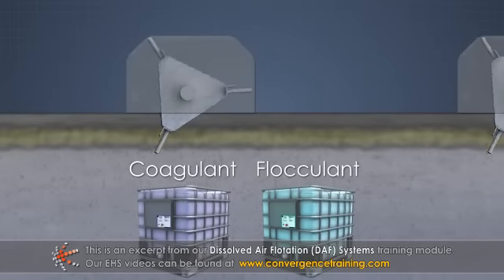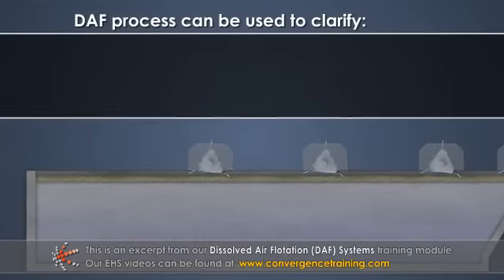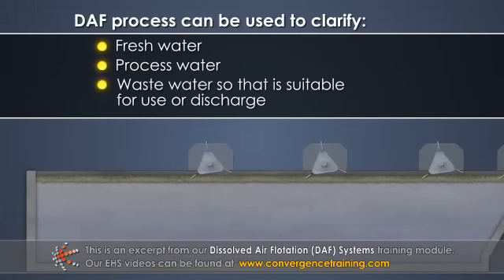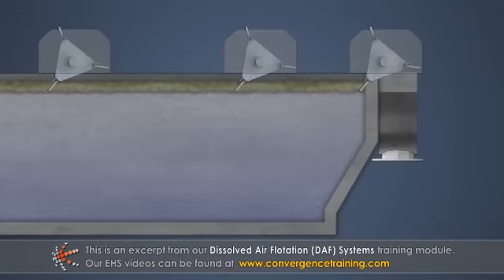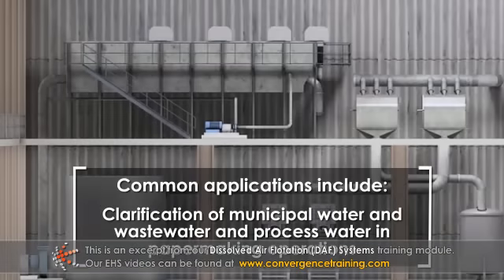Chemicals can be added to the feed water to improve solids removal. The DAF process can be used to clarify fresh water, process water, and waste water so that it is suitable for use or discharge. In some cases, the solids are collected for reuse. Common applications include clarification of municipal water and waste water, and process water in papermaking operations.